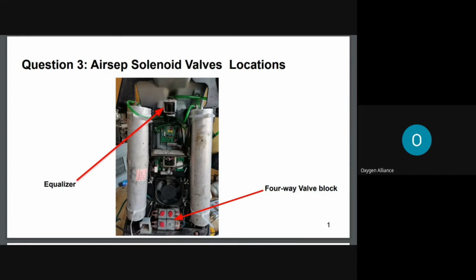Just to put in a comment on this, honestly, I've tried doing this, taking the equalizer valve and swapping it on the valve block. They actually physically fit when you try and interchange them, but as Chimwemwe said, over time, because it's supposed to draw less current, you get low purity on the oxygen concentrator because it starts underperforming.